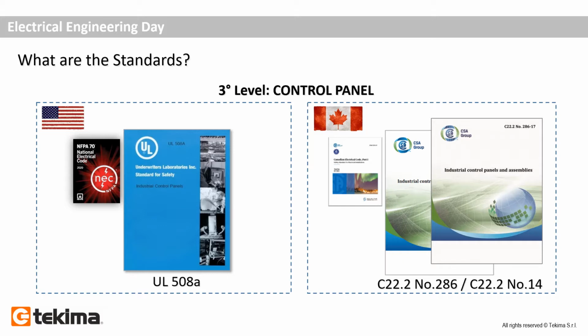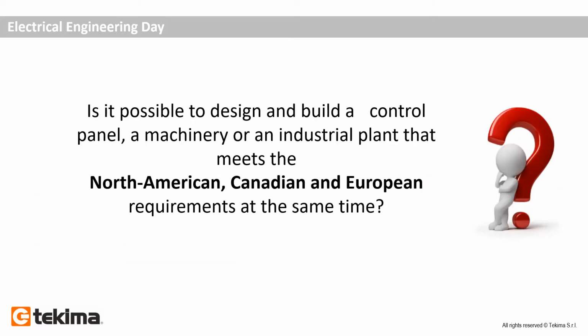In the third level, we have one main document for United States, UL 508A, and two standards for Canada, C22.2 number 286 and C22.2 number 14. As we have seen on the previous slides, depending on whether we are in Canada or United States, and depending on which type of wiring I'm making, first, second, or third level, I have to apply a significant number of different standards. If I have to sell the same machine or plant in Europe as well, I must also apply the CE standard that we already use today.